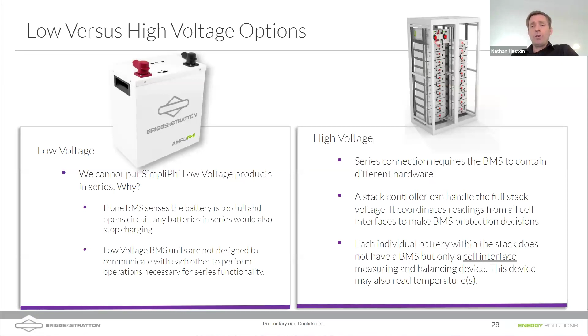So never place low voltage systems in series -- they're always in parallel. For the high voltage systems, these batteries come in either 24 or 48 volt options. We make both in Oxnard, and they use what's called a stack controller. These batteries can go all the way up to 1200 volts with our stack controllers, and they have cell interfaces which monitor the health of the individual battery modules. These systems can get very large -- I'm showing just a single computer rack stack of the high voltage stuff, but you can do a whole container of these systems.